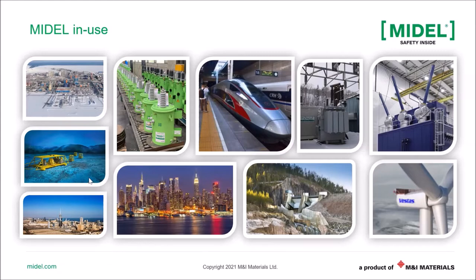Below that, what you're seeing is a substation that is located at the seabed. From the picture, it may not look that big, but this is as big as a football field, maybe a little bit bigger than that. And the transformer there is filled with MIDEL ester because it can withstand the pressure at the bottom of the ocean. Below that is another application on the other end of the spectrum as far as temperatures go. This is Kuwait City, where it can get close to 50 degrees Celsius, and MIDEL esters are used in those transformers as well because they can handle the higher ambient temperatures.